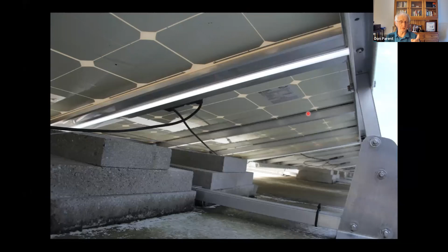And what was found is that the field connections were made not with MC connectors, which is a brand, but with Amphenol connectors. And apparently, they're not compatible with each other. And that creates the risk of a bad connection. They look compatible with each other. They actually snap together. But there have been instances of much smaller fires, but documented incidences that have occurred as a result of connector mismatches.